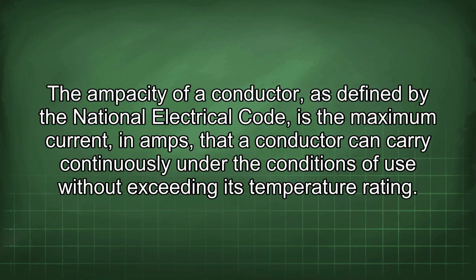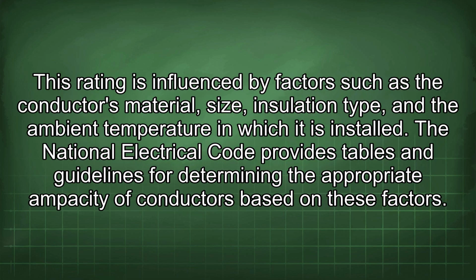The ampacity of a conductor, as defined by the National Electrical Code, is the maximum current in amps that a conductor can carry continuously under the conditions of use without exceeding its temperature rating. This rating is influenced by factors such as the conductor's material, size, insulation type, and the ambient temperature in which it is installed. The National Electrical Code provides tables and guidelines for determining the appropriate ampacity of conductors based on these factors.